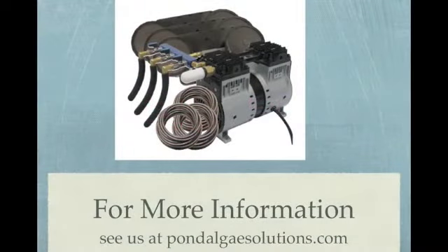easy it is to repair one of these rocking piston aeration compressors. It's a pretty simple, straightforward process, and it just takes a few simple tools. Normally when we see this repair done, you can expect another 2, 3, 4 years out of the seals that are put in there. In some exceptional cases, we've seen several rocking piston compressors go up to 10 years before they needed the seals replaced.